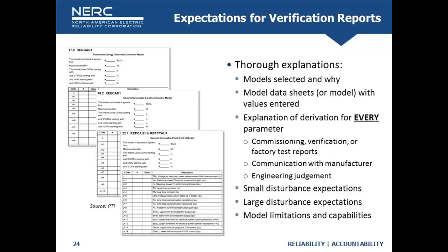But so each of the models selected, REGCA, REECA, REPCA, whatever the model is you're using, should have a description of, okay, here's why I picked that model and here's what I'm representing. You should have very clear data sheets, every model parameter shown with the value that's to be entered, and an explanation or derivation for every single model parameter. Doesn't necessarily mean it has to be a test. You could have a commissioning test that gets you some of your parameters. You could have type tests, factory tests that Bob alluded to that show some other parameters, particularly at the turbine level. You can have the verification test report itself that can get you additional parameters, particularly on the plant level controller, for example.